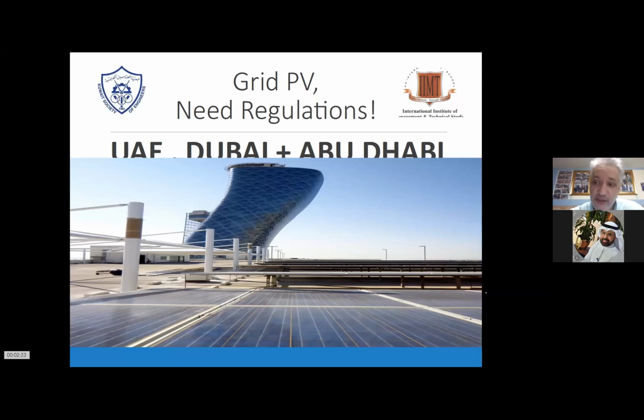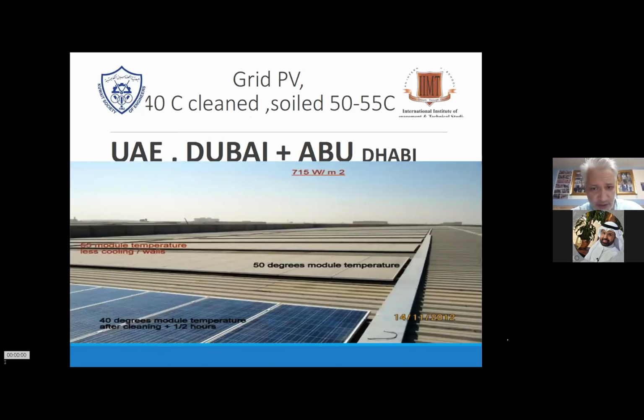There is no equipotential grounding in between the facility, so the house. It's worse with a concrete roof, with corrugated roofs or with roof sheets, because you have a capacitor. Here it's a concrete roof with a parking deck earth, and like I said, it went straight to the ground, but no interconnection. So here in this example, it was enough just to make two earthing connections towards the inverter, and then you had the same input as the output.